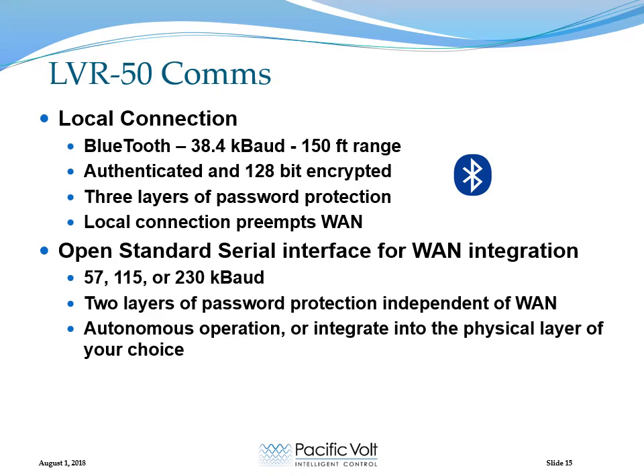The regulator comes with a Bluetooth interface which runs at 38.4 kbaud. It has a range of approximately 150 feet, and we call this the local connection. It's primarily intended to give access to the regulator's operating parameters, the fault log, that type of thing. All the data files are also accessible for download through this interface, but it's painfully slow because the data files are typically quite large. In addition, we offer an open standard serial interface for wide area network integration. We typically don't supply any hardware for this because every utility seems to have their own idea of what the ideal solution is. But it's open standard, and we can help you integrate whatever hardware you prefer into this.